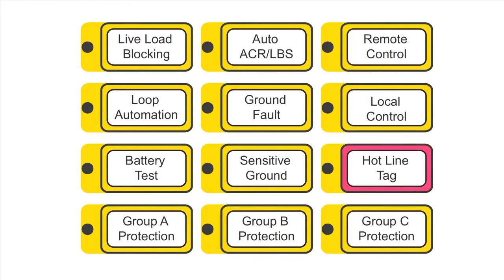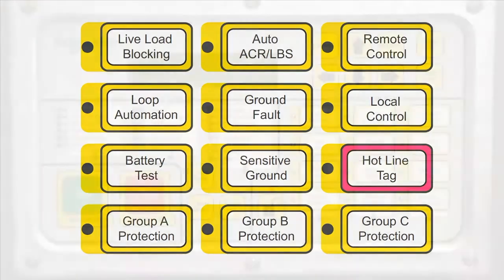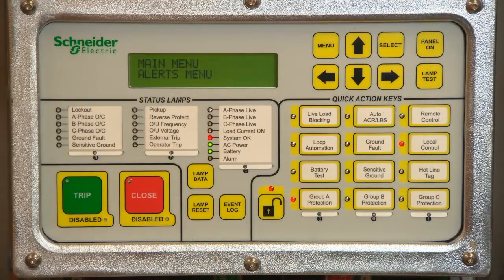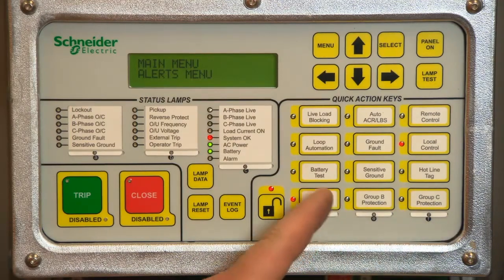Hotline tag, or work tag, is applied using this key. Work tagging ensures that closing cannot take place and also activates the work tag protection settings. To activate or deactivate any of these keys, you must first press the lock button. The green indicator will reset to a red lock state if no selection is made within a 20-second window.